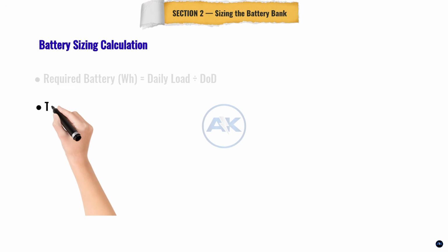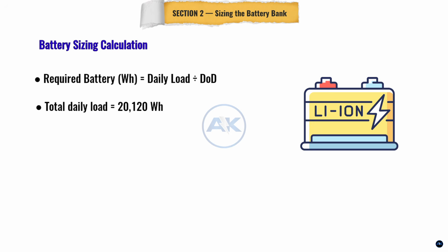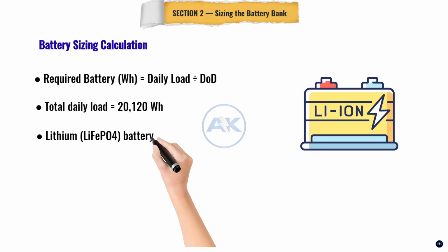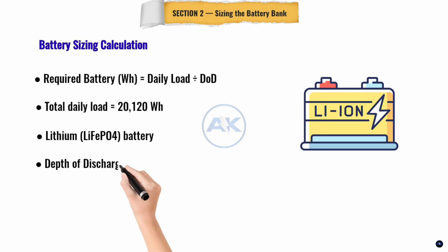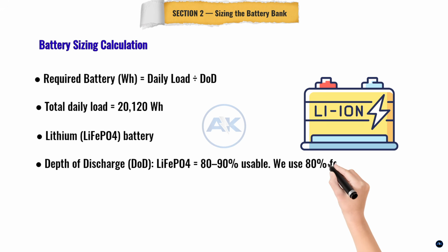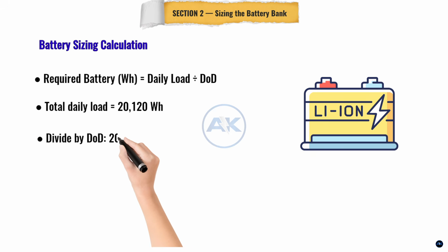Section 2. Sizing the battery bank. Now that we know our daily load, we can size the battery bank. We are using lithium iron phosphate, LiFePO4, batteries. These are the best choice for solar systems today. They last over 3,000 charge cycles. They are safe, efficient, and they allow us to use 80% of their capacity, what we call depth of discharge. Lead-acid batteries? You can only use about 50%. That means you need almost twice as many. LiFePO4 wins every time.